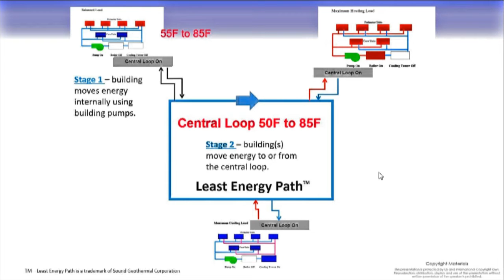So what happens if it gets below 50 or above 85? Well, I'm thinking, can I stand this? What do I want? A heat pump typically has a 7-degree drop in heating, 10-degree add in cooling. So maybe I'm going to start looking at a cooling tower around 85, maybe 86. But the first place I'm going to go is my loop, because I added another small pump, and I either have energy stored in there or I'm able to receive energy, so I'm able to touch the system. It may be just enough to keep me from firing a conventional piece of equipment, and historically it has been, big time.